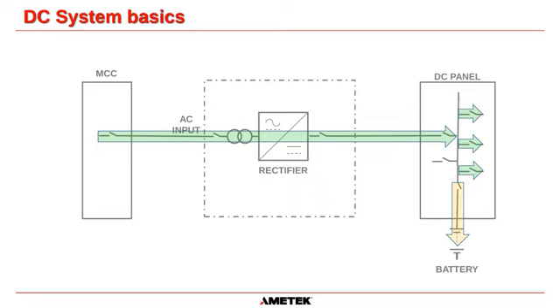As you can see on the screen here, this is truthfully how we think the best DC systems are designed. So you have your MCC that feeds AC into a charger or rectifier. It's usually a 480 volt three-phase supply in the US, 415 volts in Europe. That goes into the AC input of a rectifier, and then that rectifier changes the AC into DC. And then that DC should go to a DC panel, which then feeds the load circuits, and that should also be where your battery is connected.